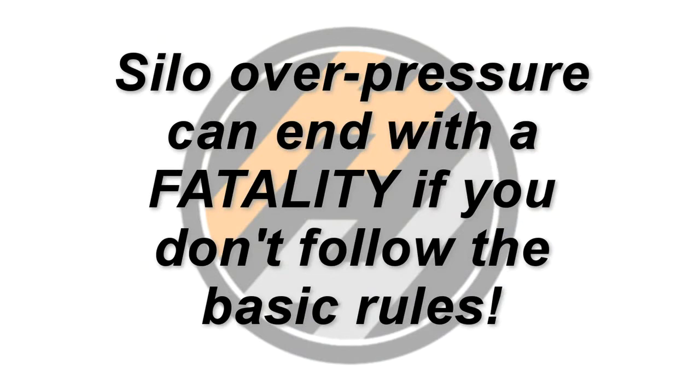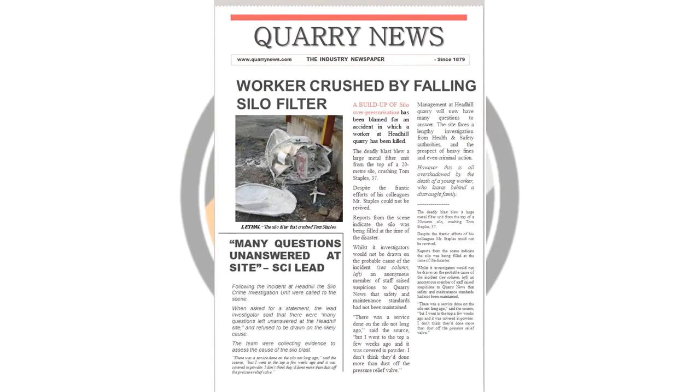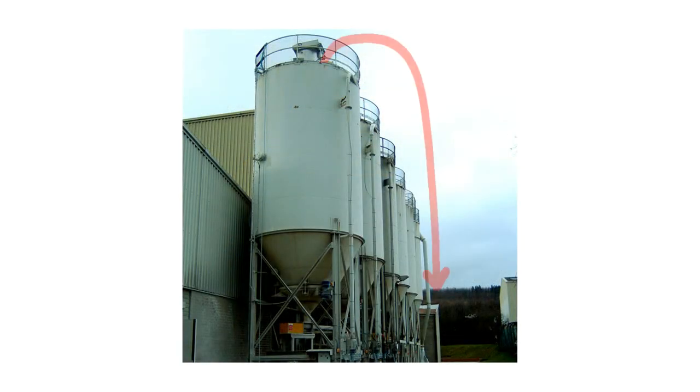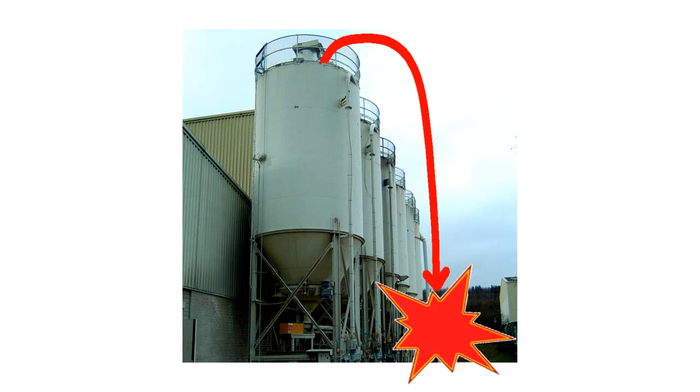These three basic rules are essential as silo over pressurisation is a very serious risk on sites. If air used to convey product from a tanker becomes trapped inside the silo, this results in over pressurisation. This can easily blow a filter unit off the top of the silo creating a potentially lethal danger.